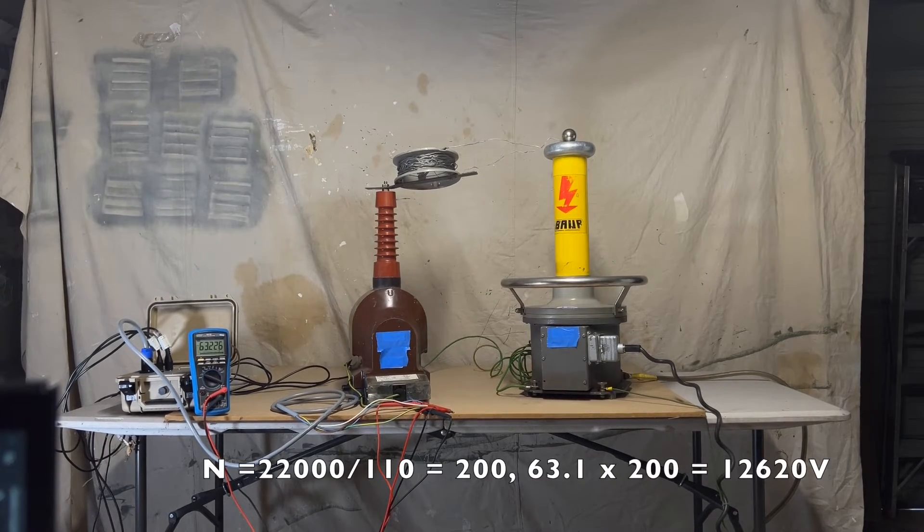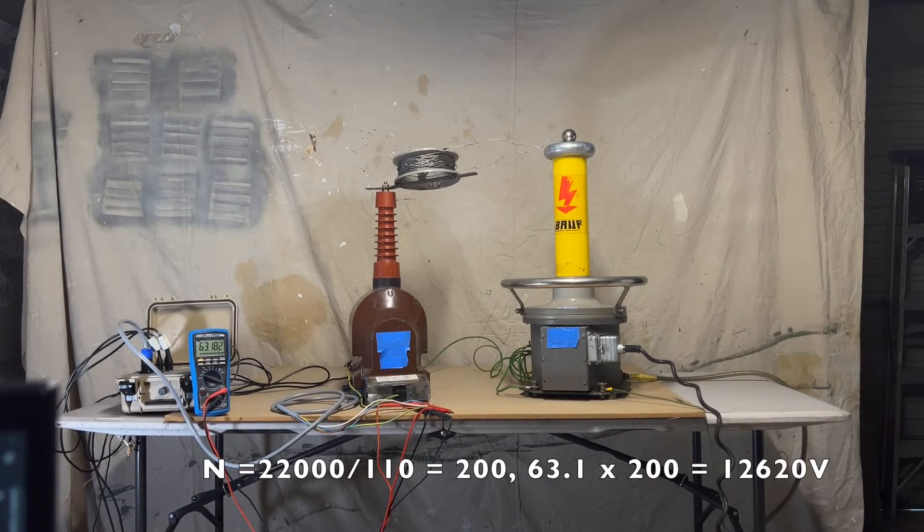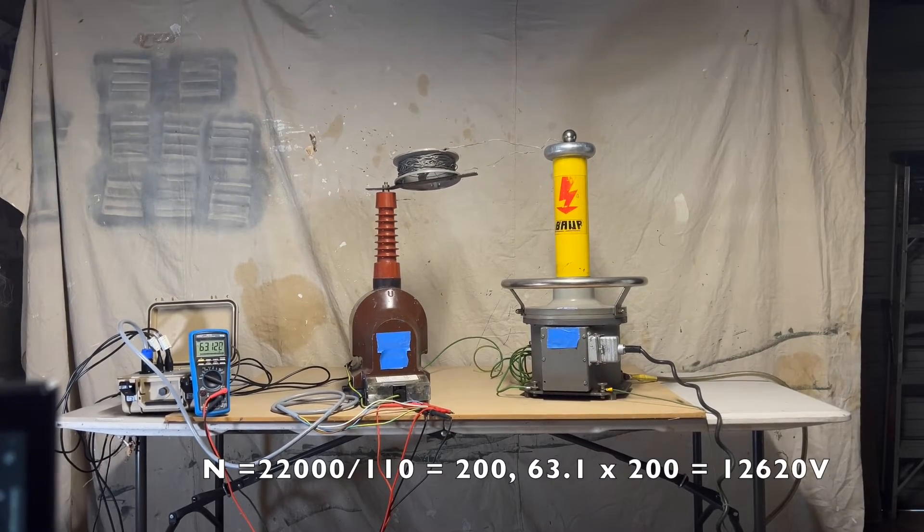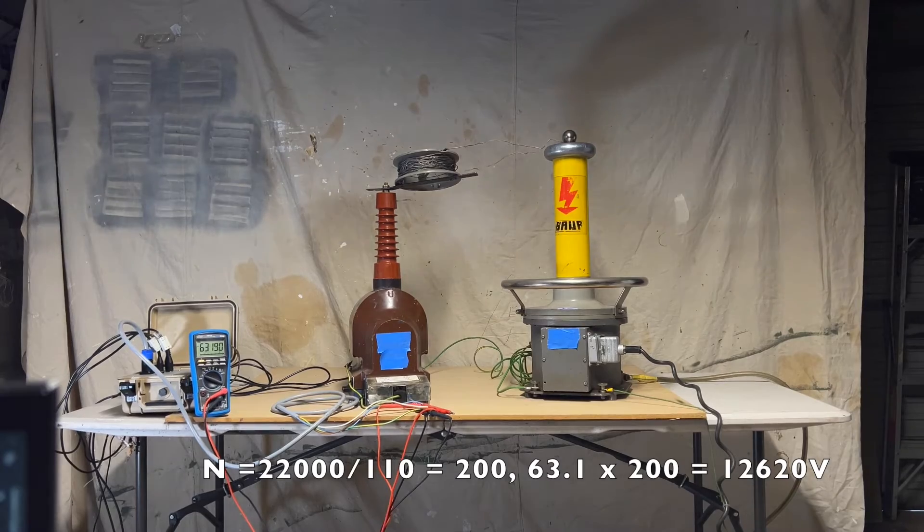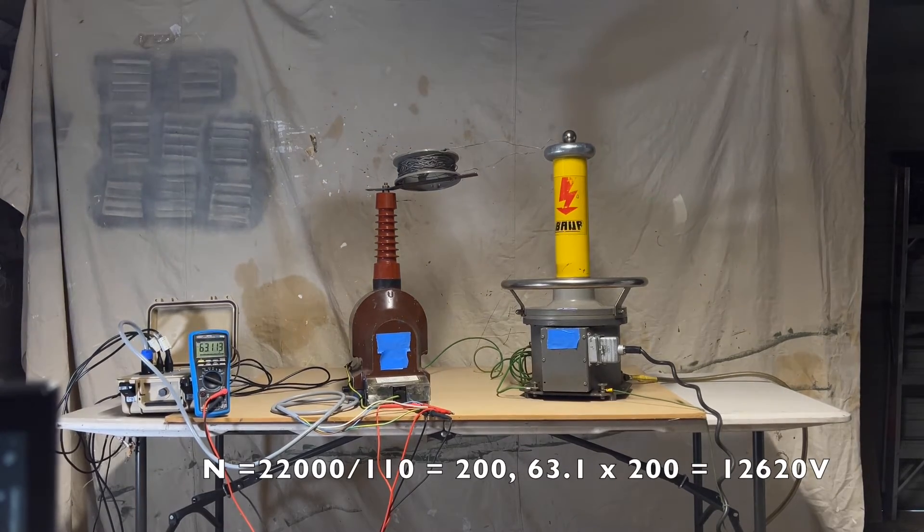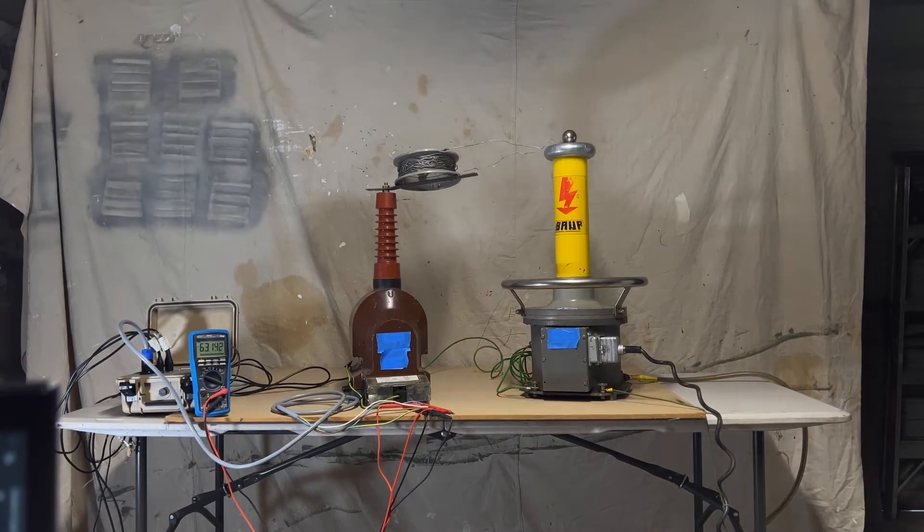So this is 22,000 on root 3 to 110 on root 3. So 63.1-ish equates to 12,700 volts on the top of the wire there at the top of the coil.